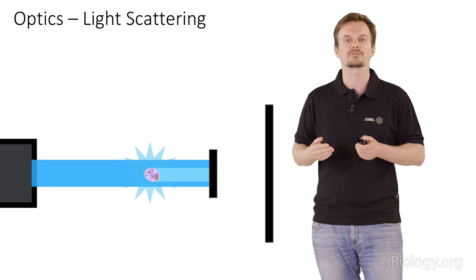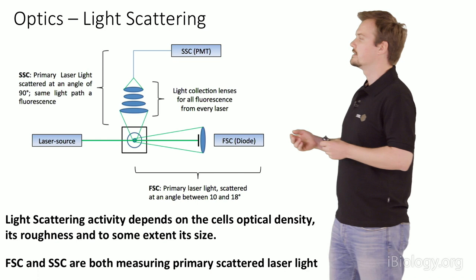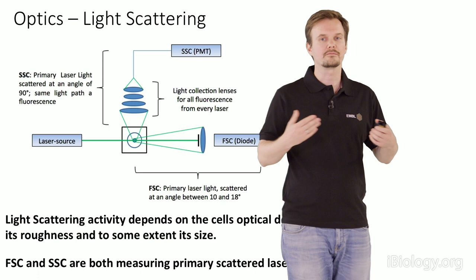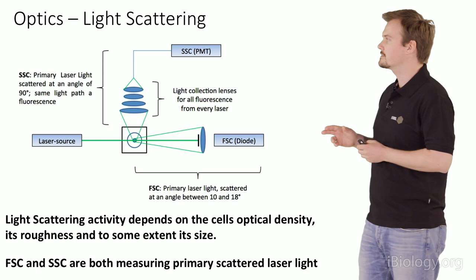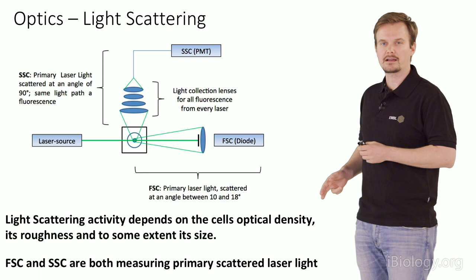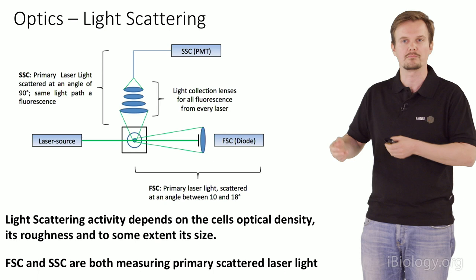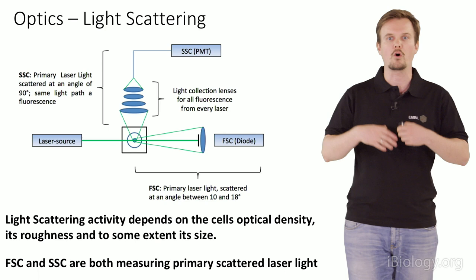Because light scatters omnidirectionally, we don't only generate a forward scatter signal — we also generate a side scatter signal. Most instruments take this at 90 degrees orthogonal to the primary laser light, which is simple to build and very precise. Light scattering activity depends on the cell's optical density, its makeup, its surface roughness — membrane protrusions can induce more scattering — and to a certain extent also its size, though not predominantly. These are all merging functions together.